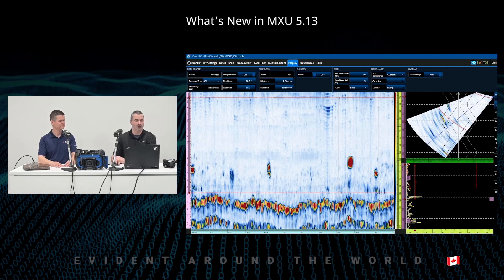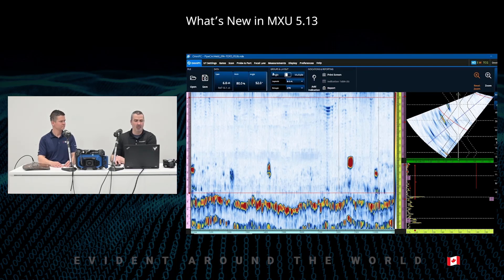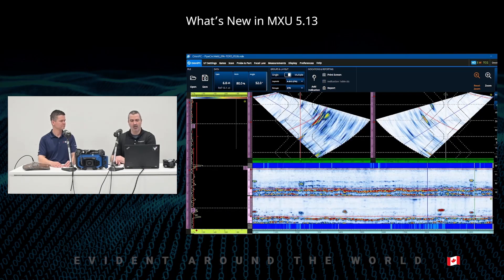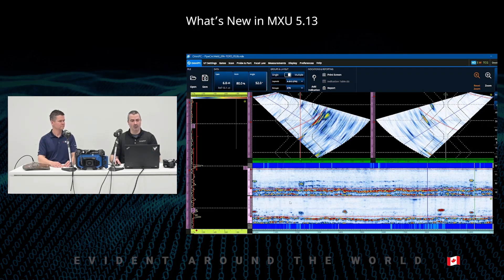We're left with our geometry line and all of the indications — very clear, very easy to understand. Going back to the main screen and activating the multiple display, we now have two merged B-scans left with only the indications: one, two, three, maybe four, five, and six. Very easy to see, very easy to understand.